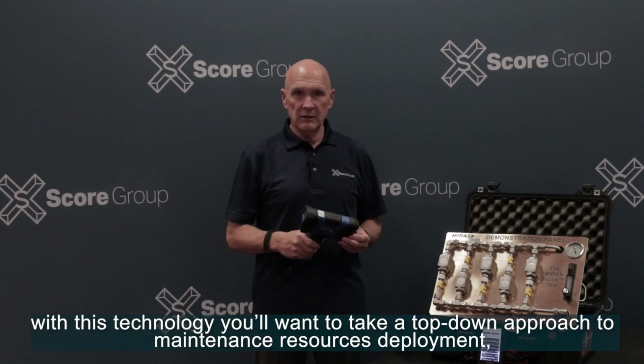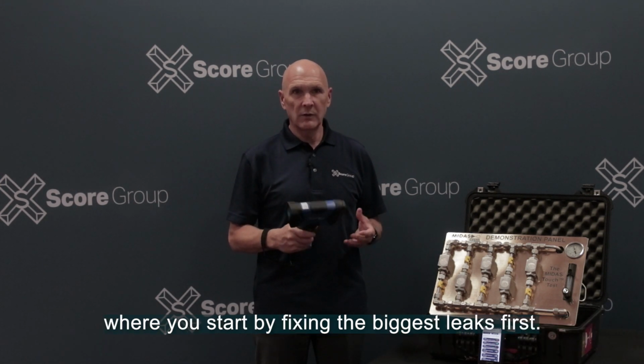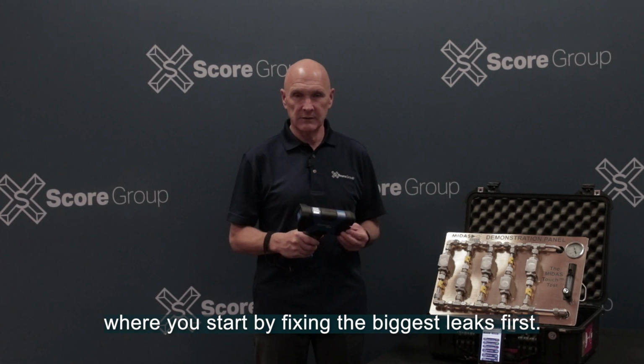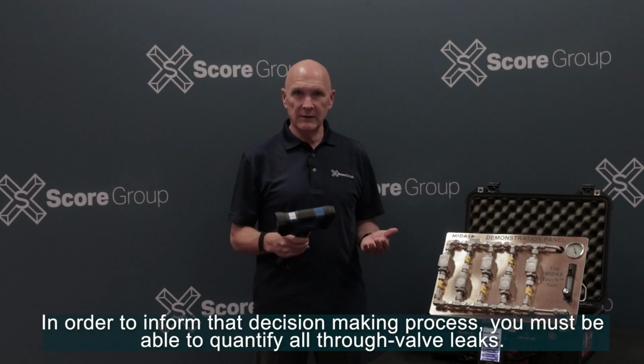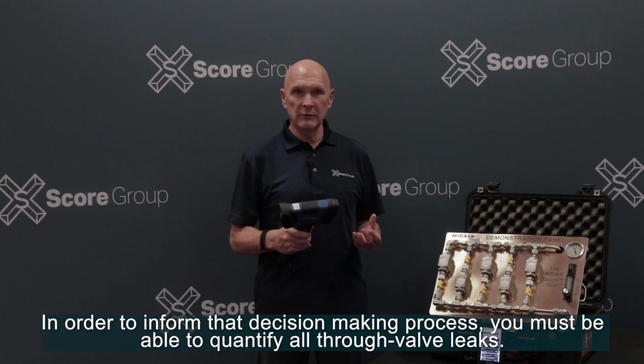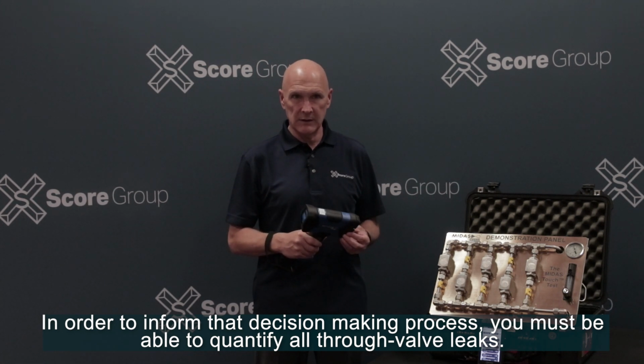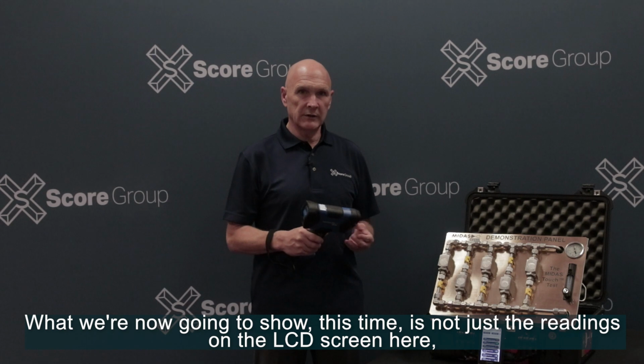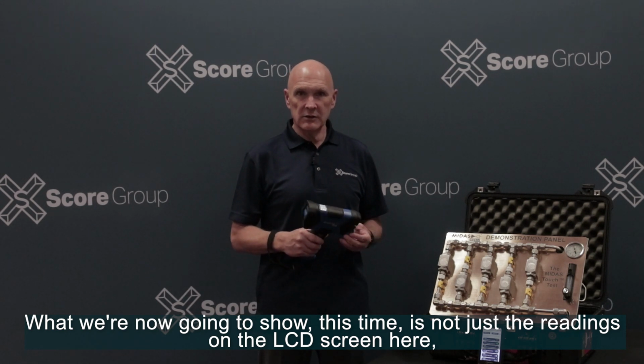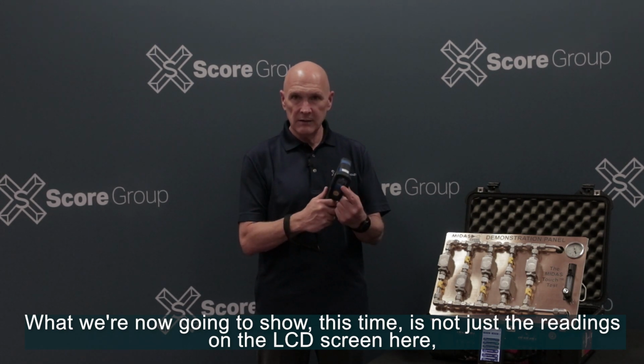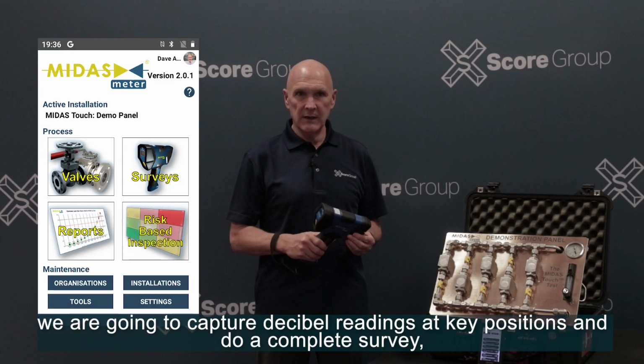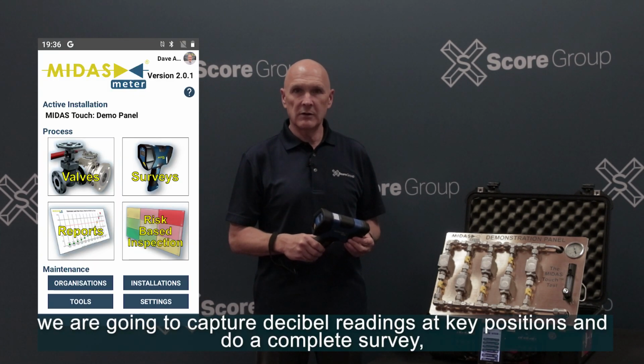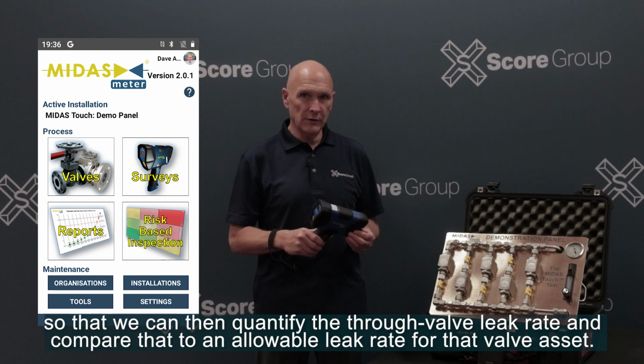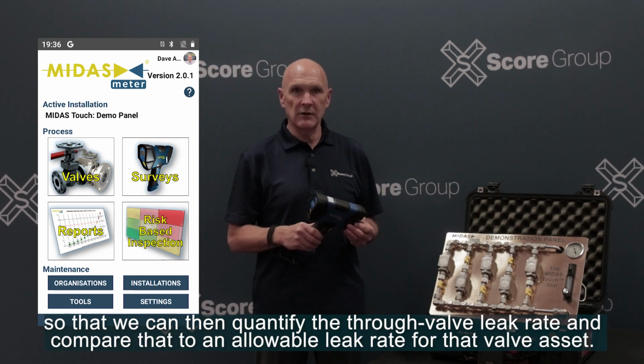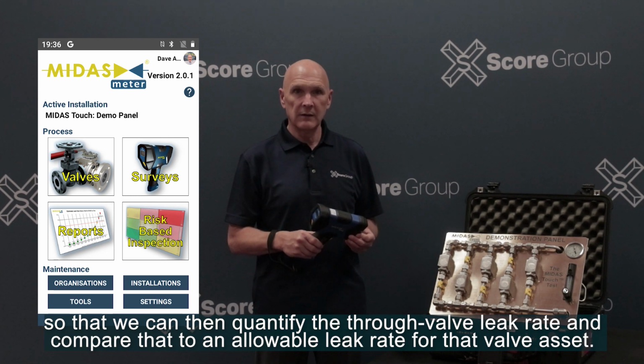With this technology, you'll want to take a top-down approach to maintenance resources deployment, where you start by fixing the biggest leaks first. In order to inform that decision-making process, you must be able to quantify all through valve leaks. What we're now going to show, this time, is not just the readings on the LCD screen here, but we're going to capture decibel readings at key positions and do a complete survey so that we can then quantify the through valve leak rate and compare that to an allowable leak rate for that valve asset.